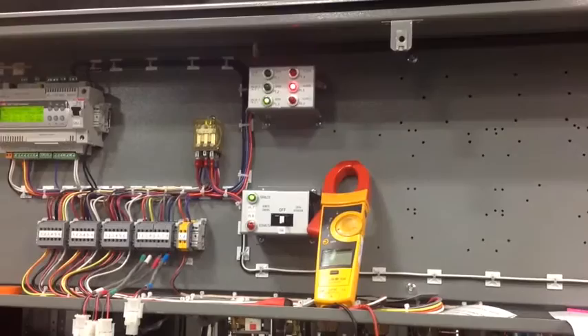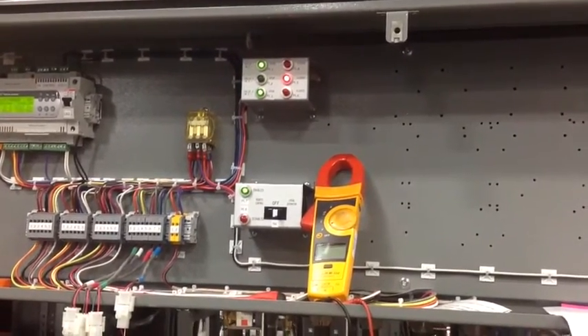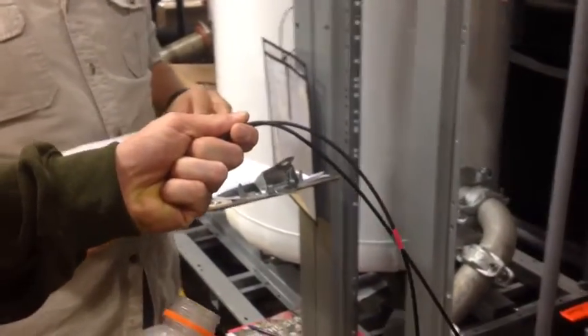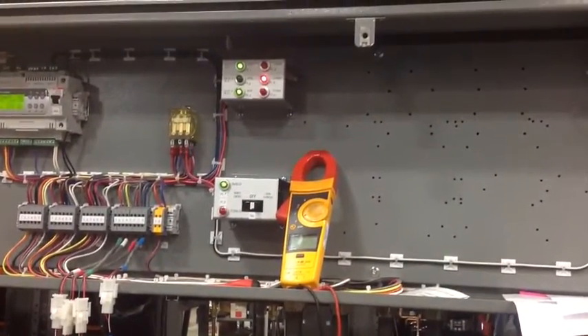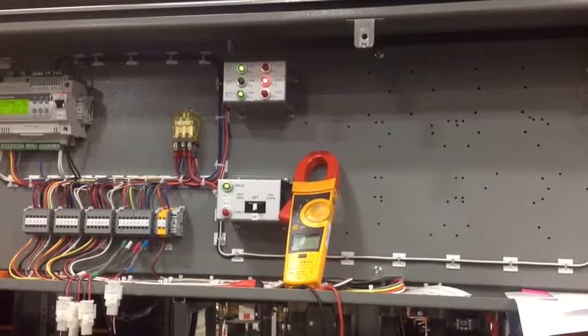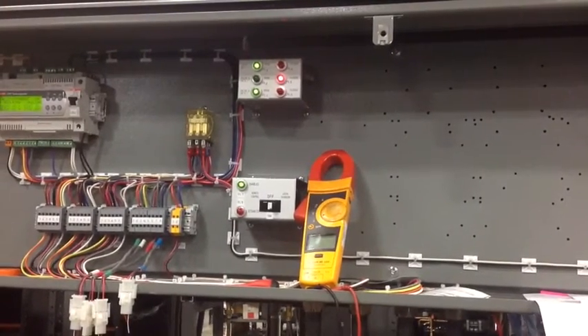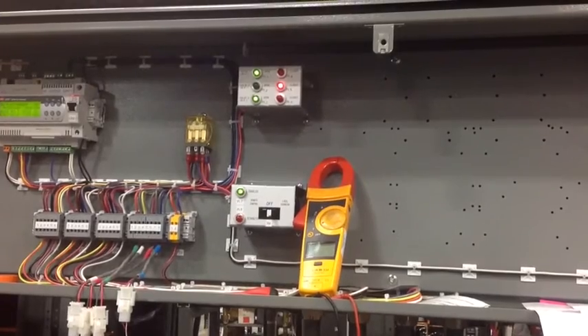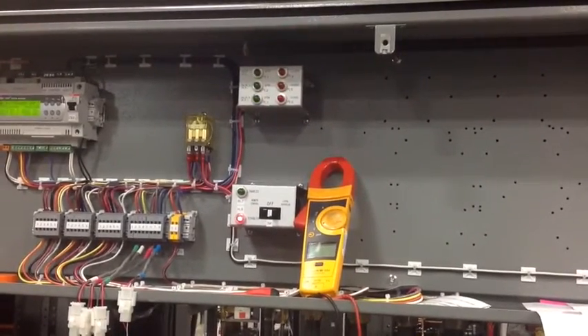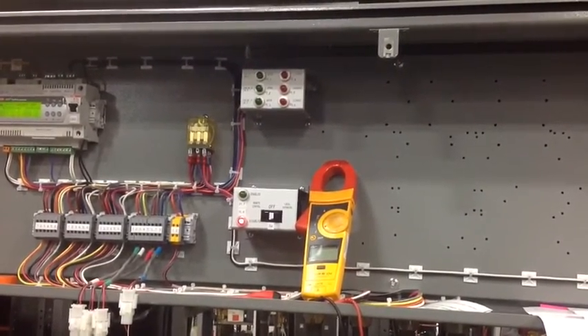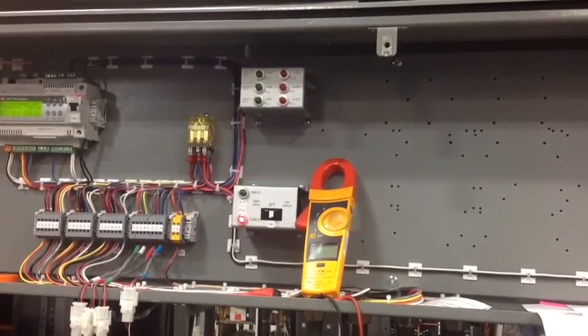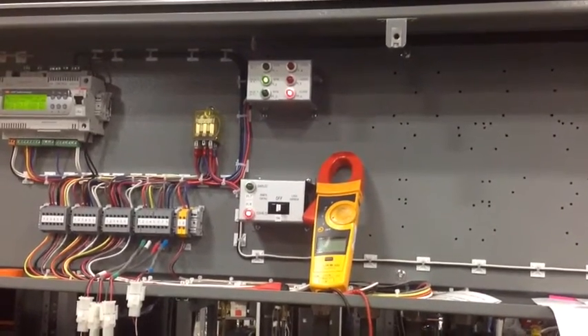You'll notice that the indicator lights have switched the position of the 3 valves. The middle valve in bypass and the isolation valves for the heat exchanger open. Now we pull the temperature probes out and warm them up, again simulating now warm water coming from the comfort loop. This will cause the indicator lights to flip, where the bypass valve will go open, that's the middle valve, and the 2 isolation valves for the heat exchanger will go closed. And you'll see that here in just a second. You'll also notice that the bottom indicator light is red, that it is off.